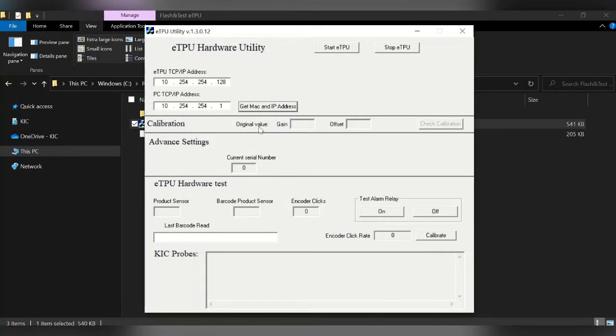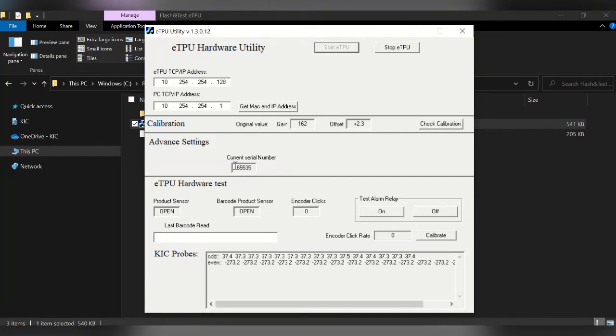Now save and exit. Please note, for single systems, the eTPU TCP IP address is 10.254.254.128, but for dual lane systems, one of the eTPU IP addresses will end with .129 and the other with .130. To start the communication with the eTPU, please click on Start eTPU button. You will notice that the button will be grayed out. Some of the fields will be automatically populated, like the current serial number, and the buttons are now activated. To confirm this communication, you can also see the current probe temperature values under KIC Probes.